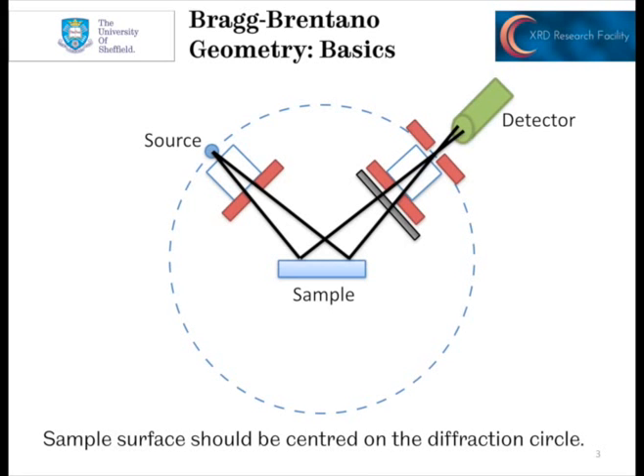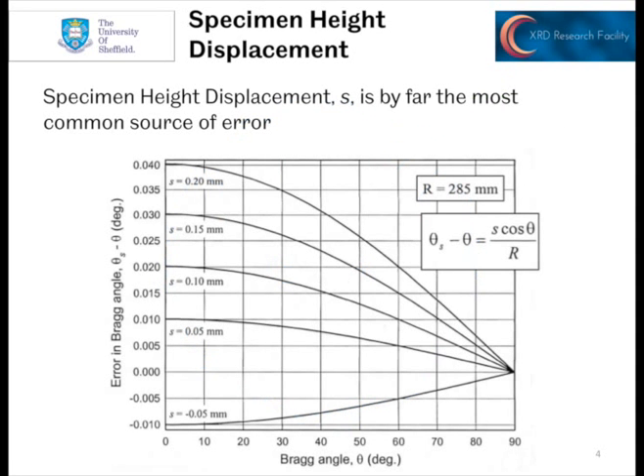So in this video we're going to be looking at various of these apertures. What's key about this, looking at this basic schematic, is that the sample surface is in a very specific position — the top of the sample surface should be on the diffraction circle. If you took a point right at the centre of the sample, right at the top, that should be on the centre of the diffraction circle. It should be self-evident what would happen if the sample was instead shifted to a higher position: it would intercept those X-rays coming in from the source sooner and diffract them at a higher angle. This is the cause of the so-called specimen height displacement error, which is by far the most common source of error in diffraction experiments, and it's easily avoidable if you put the sample in the right place.